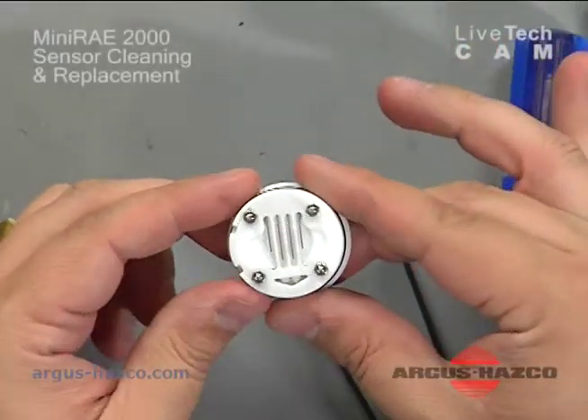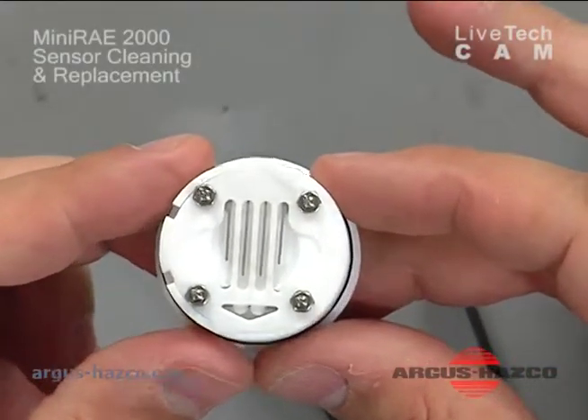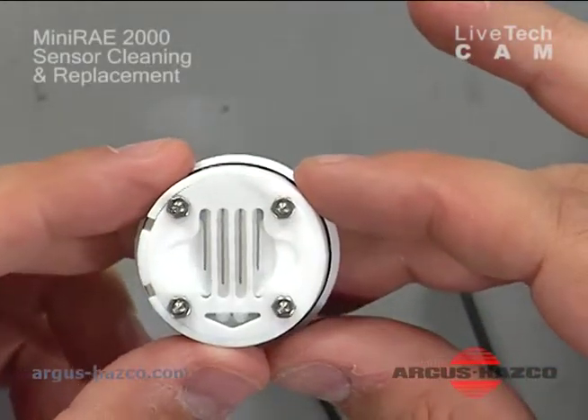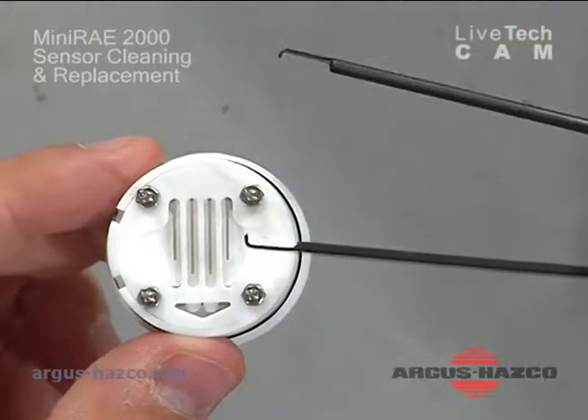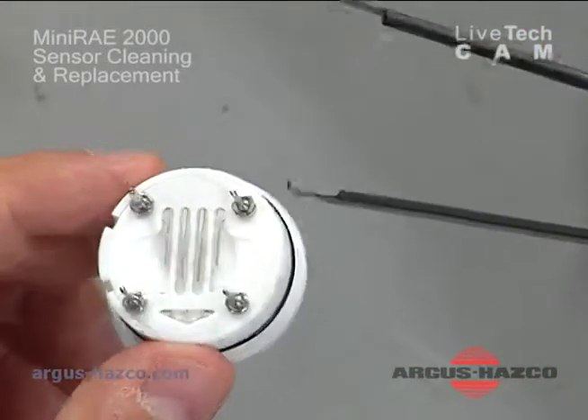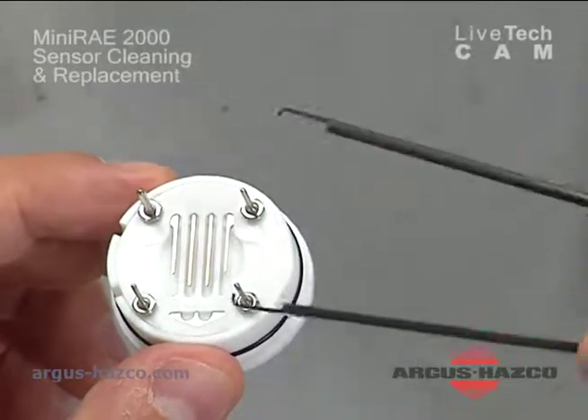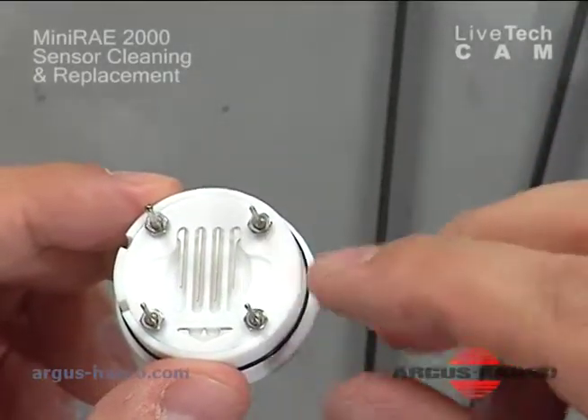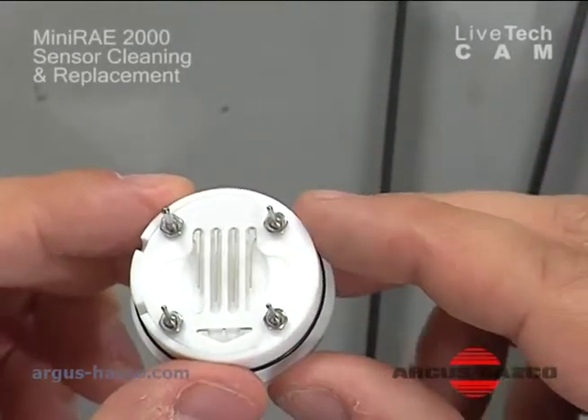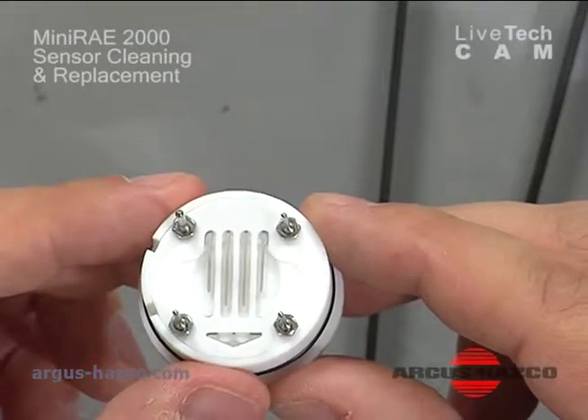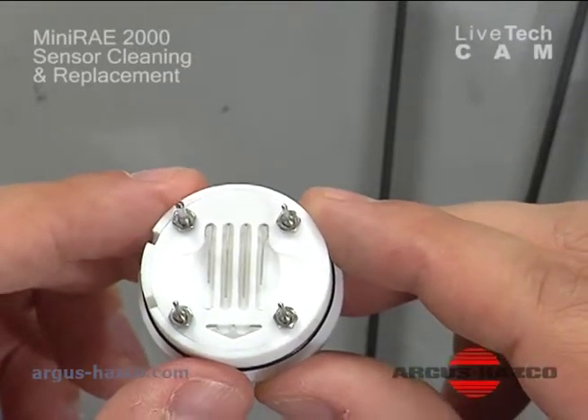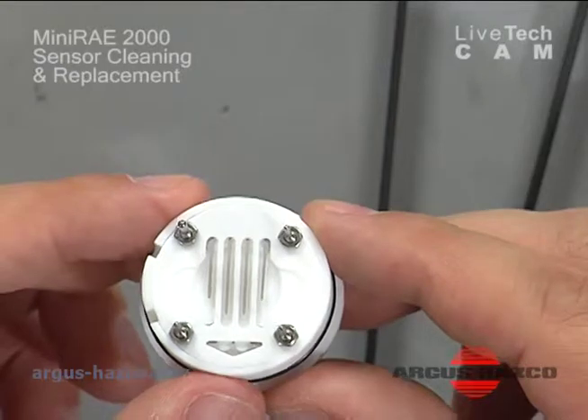If you can zoom in, that's good. To inspect it, you have the sensor here with metal pieces that bring the voltage to the sensor, along with all of the different electrodes. If you see it dirty, covered, wet, or looking even a little bit rusty in color, then you definitely need to clean it.